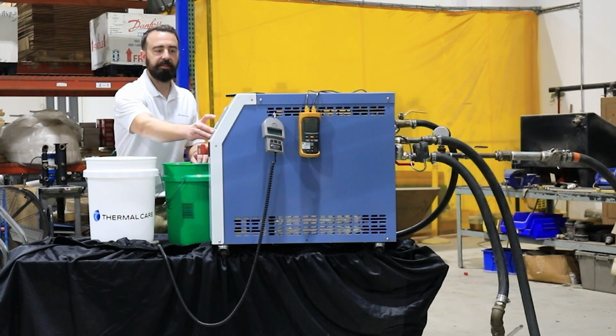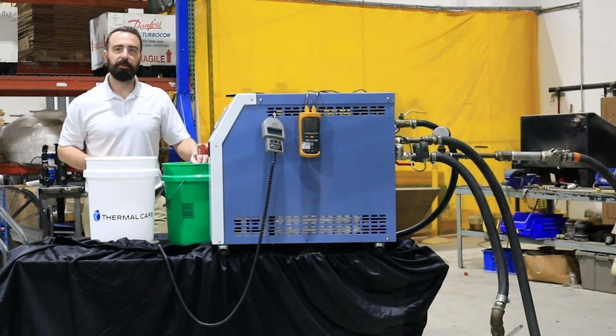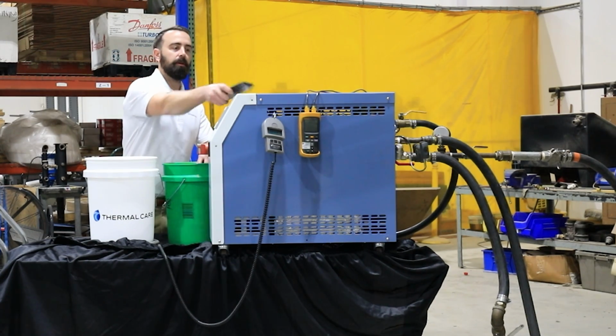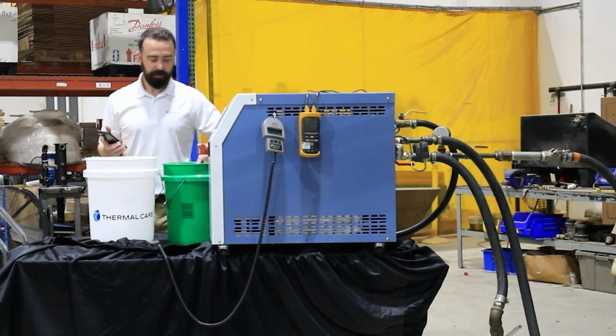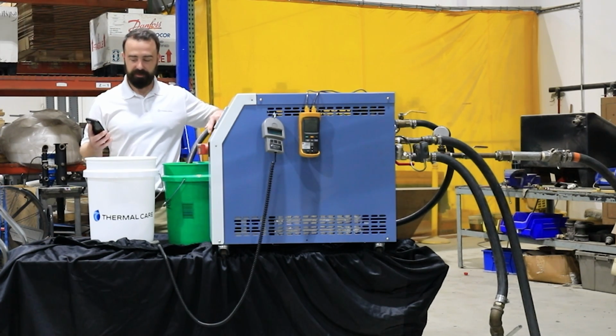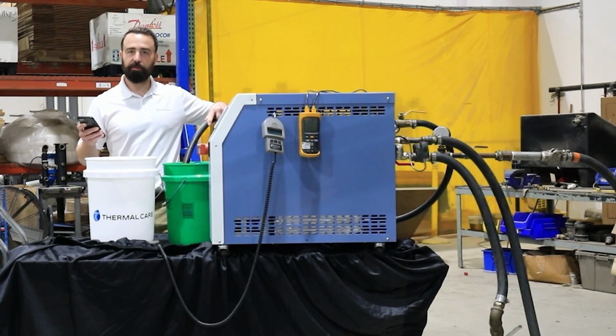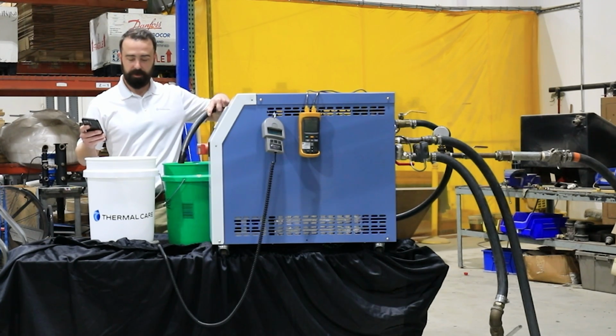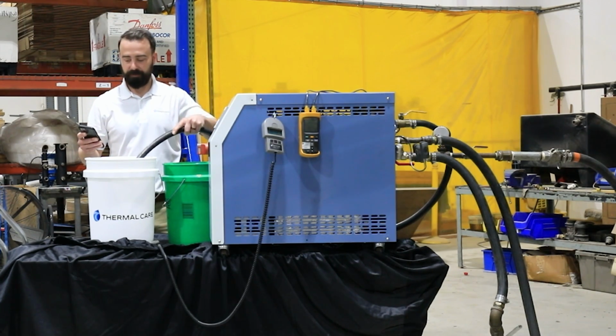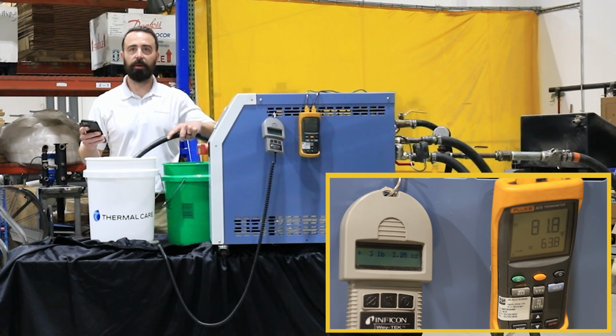Now we start the process and establish cooling flow. We want to have our stopwatch ready. We have established cooling flow, and I will switch to the weigh bucket and start the timer at the same time. And we're going. We will let this run for 1 minute, and then we will stop it and use that weight for the bucket.